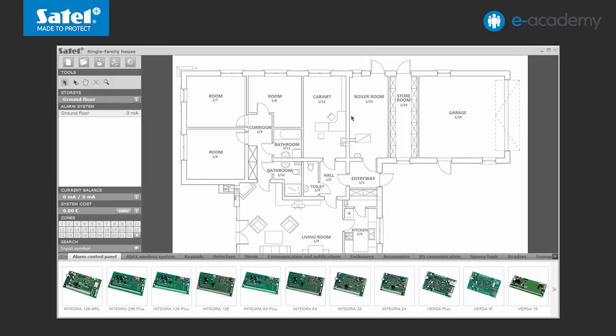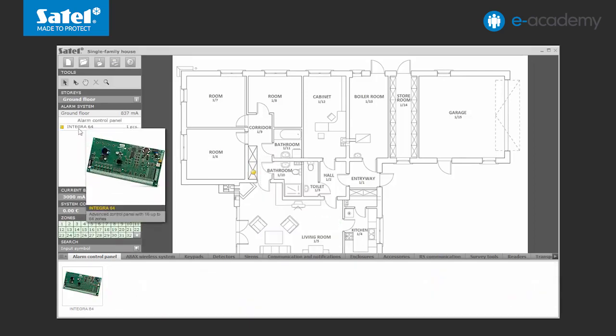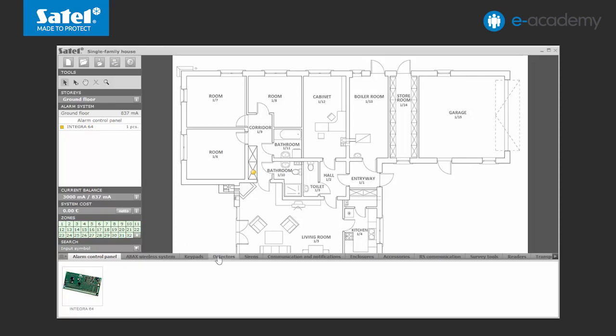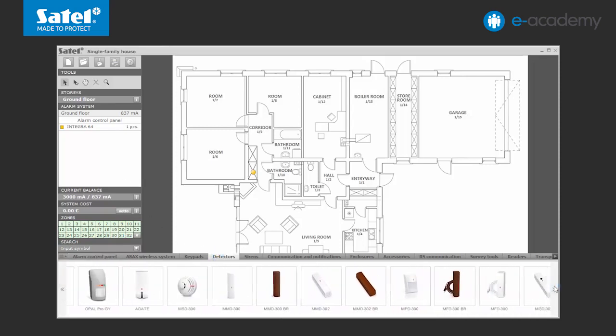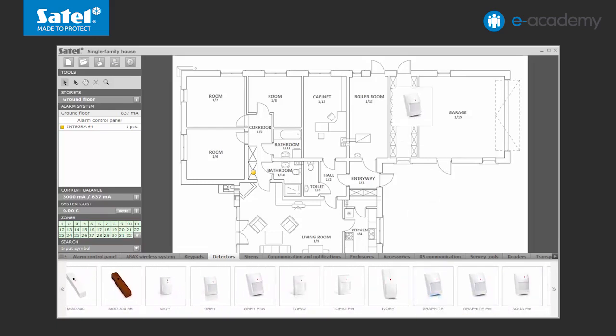Put onto the drawing, in turn, selected products from the device menu located at the bottom of the screen. The first device will be the alarm control panel, which in this case is the Integra 64. The plan location of the control panel will be shown on the drawing and its name along with information on the number of panels in the system on the list in the side menu. Further devices will be put onto the site plan in a similar way, starting with the detectors. Remember to include all areas of the building which are potentially vulnerable to threats. PIR detectors will be installed in all rooms accessible from outside in which there are windows or doors.